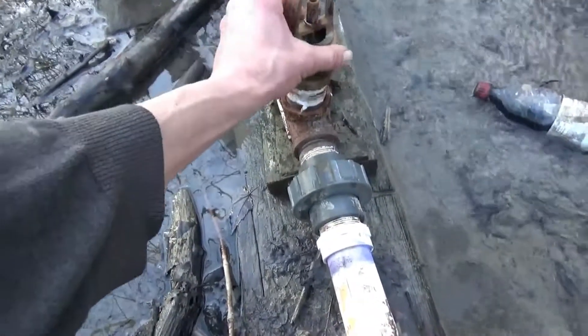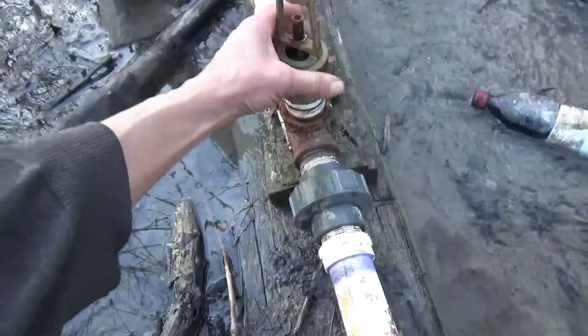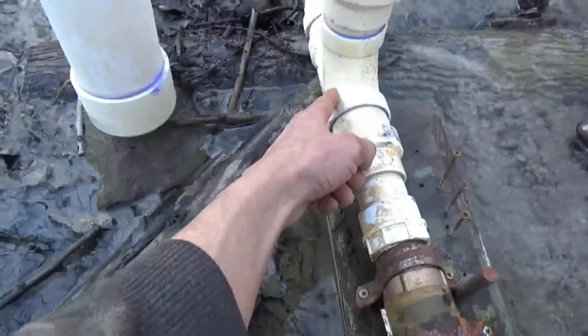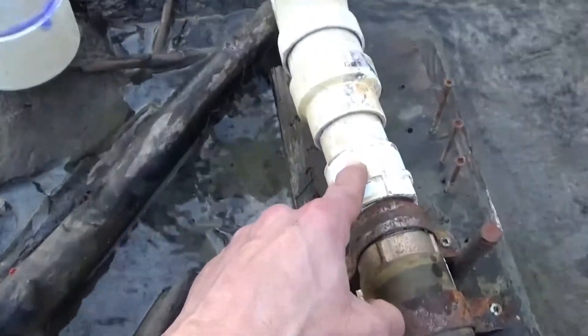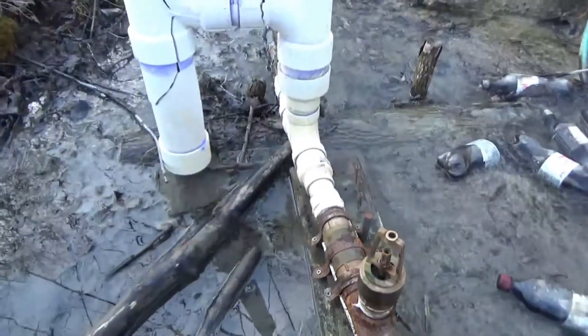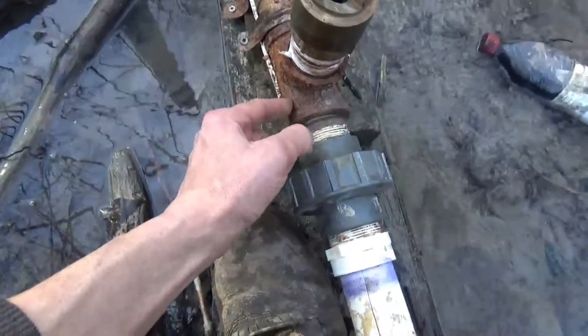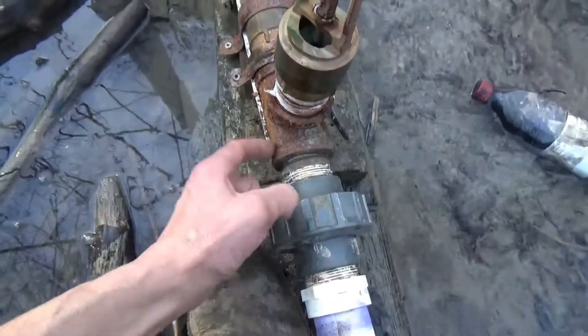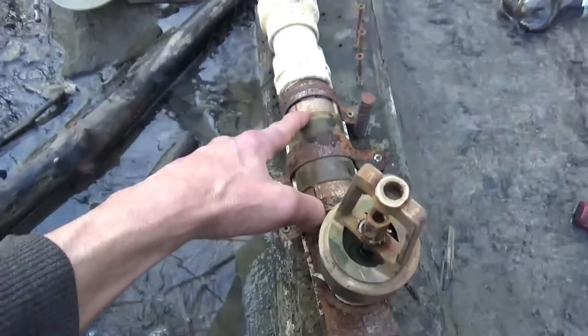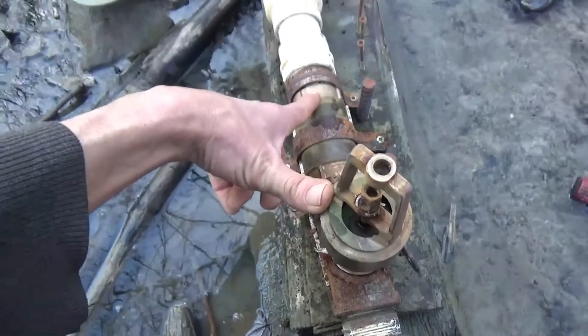We did split pretty much everything else here — fractured all the way down, all the plastic. Unfortunately, the plastic isn't nearly as expensive as the rest of it. I don't think we split any of the cast fittings, so those will be okay. And the spring-loaded check valve didn't take any damage either, and that's good because that's also about 75 bucks. Those two valves are the really pricey parts that I'd hate to have to replace.